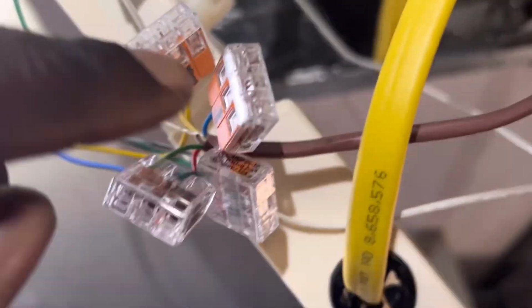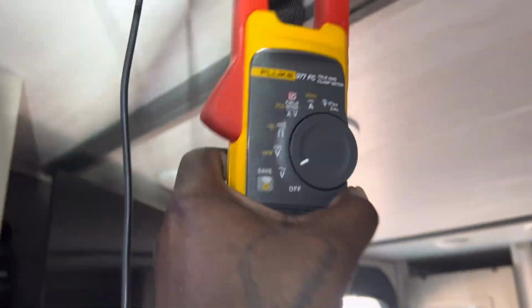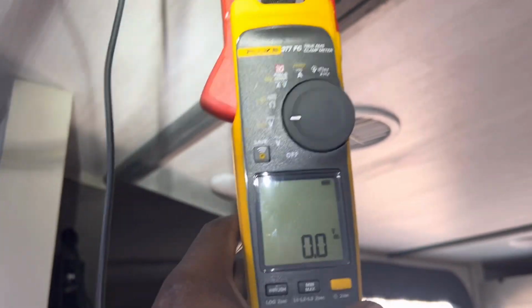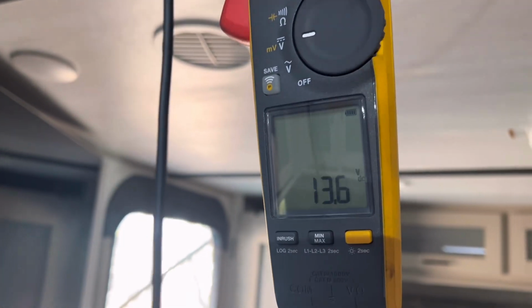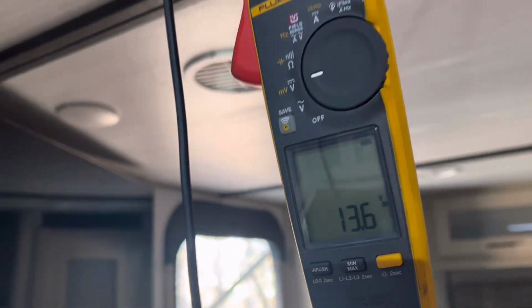Suspect a bad relay. I check my control side. I do have 12 volts on the yellow wire, which is coming from the thermostat. So if we go to volts DC, I take my probe, going into the Wago. Right now the unit is on, and as you can see, I'm inside that yellow lead, which is the Y, which is compressor.